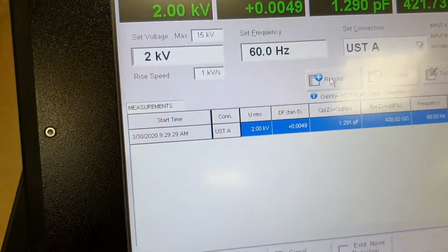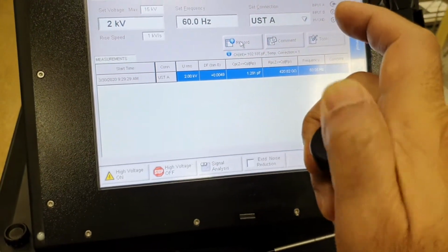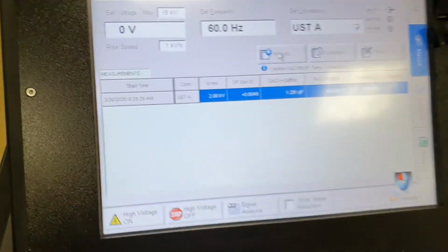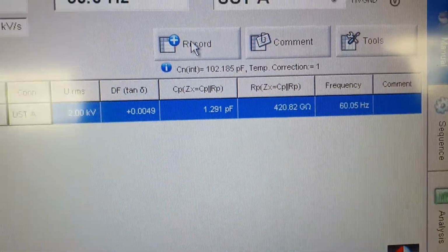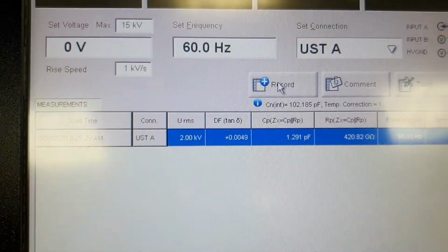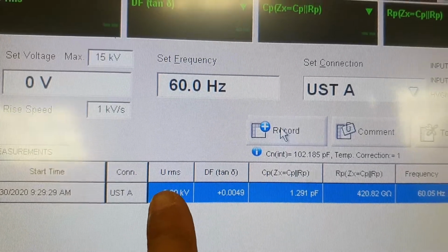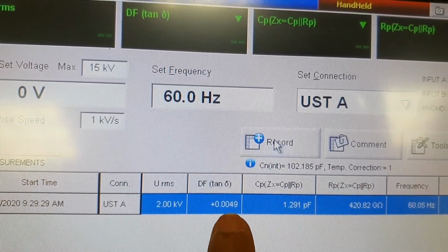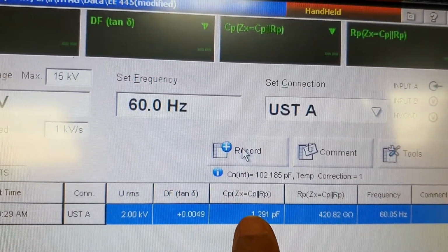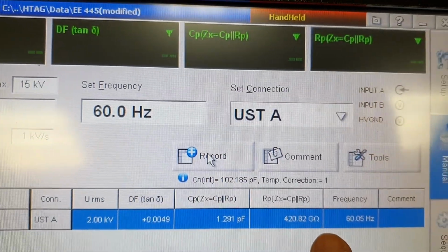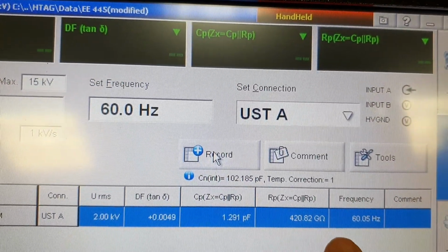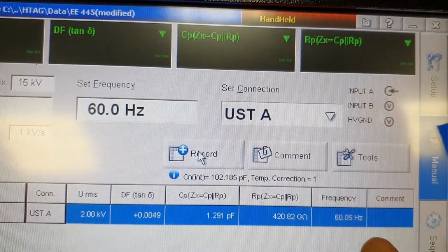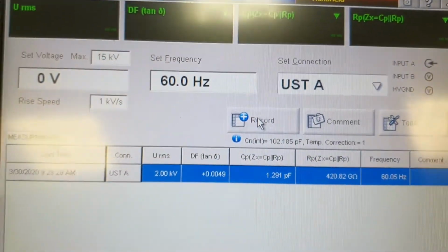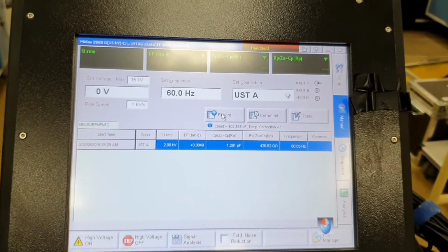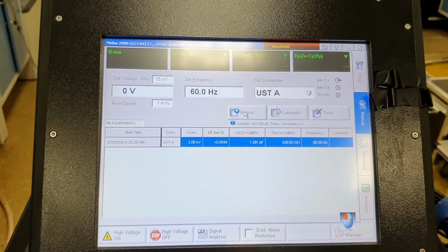Now I will release this button, so the high voltage is automatically switched off. We now have values for this XLP insulation: at 2 kV, tan delta is 0.0049, capacitance is 1.29 picofarad, resistance is 420.8 gigaohms, and frequency is 60 hertz. This is the first part of the experiment, already completed for the XLP insulation.